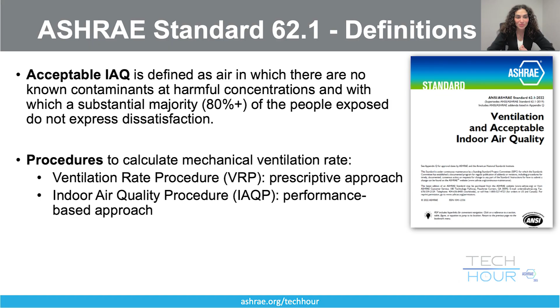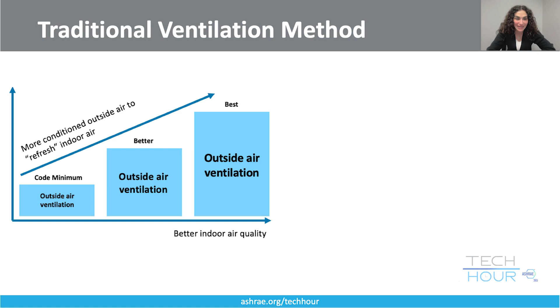To achieve this, the standard has two procedures to calculate mechanical ventilation rate—how much outdoor air do you need: the ventilation rate procedure, a widely used prescriptive approach, and the indoor air quality procedure, a performance-based approach. Historically, ventilation was viewed as the primary method for improving indoor air quality—if you want better indoor air quality, you increase your outdoor air. We've all heard the phrase, the solution to pollution is dilution. But relying on ventilation alone can be both energy intensive and carbon intensive, especially in climates with big cooling or heating loads.